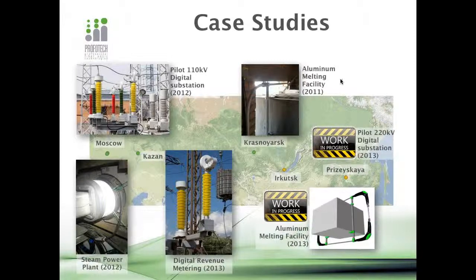Point 5 is reference applications. I would like to show you some that are made in Russia. Let's start from the upper left corner. It's a pilot 110 kV digital substation in Russia. On the slide, you can see a picture with fiber optic CTs and VTs installed on the substation. And as I said, it's a pilot, so-called digital substation. This is like an R&D center where people do some tests, and they check the work of IEDs, of protection, of metering, and so forth.